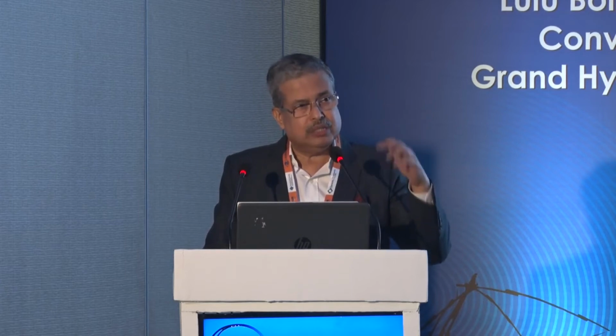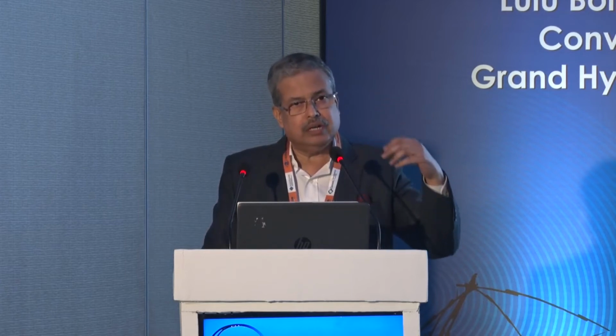Either the sequential trifocal, where there are two step heights with each one giving a little more as compared to the other. So you have one step height which gives you about 40 centimeters at near vision, and a second intermediate step height which gives around 80 centimeters.